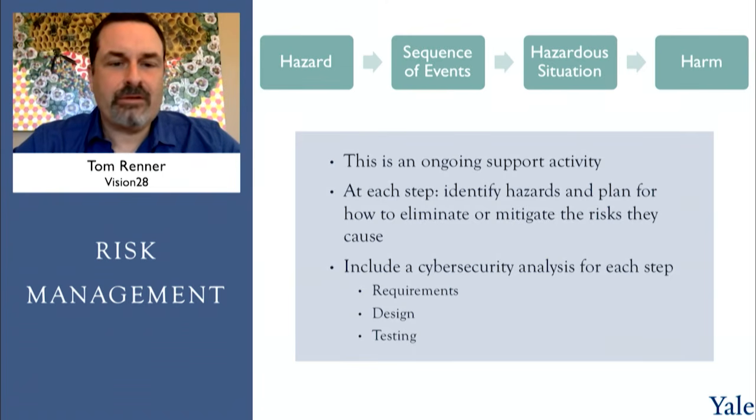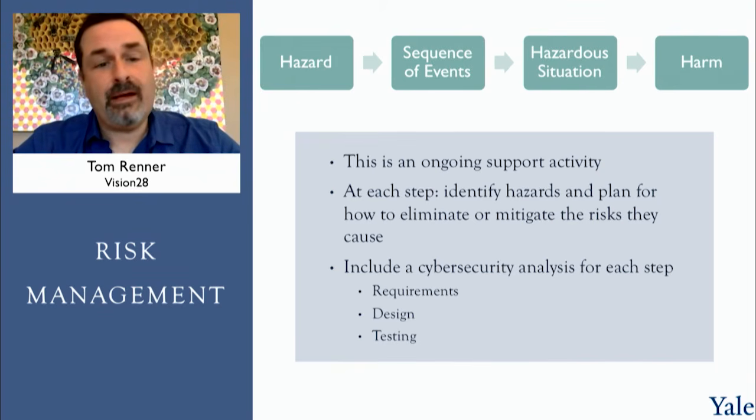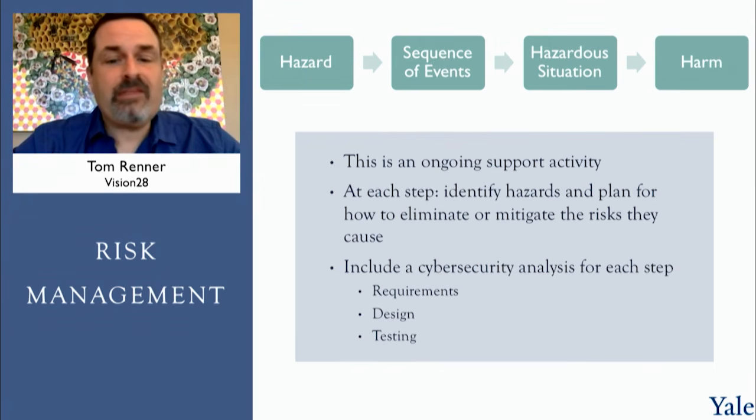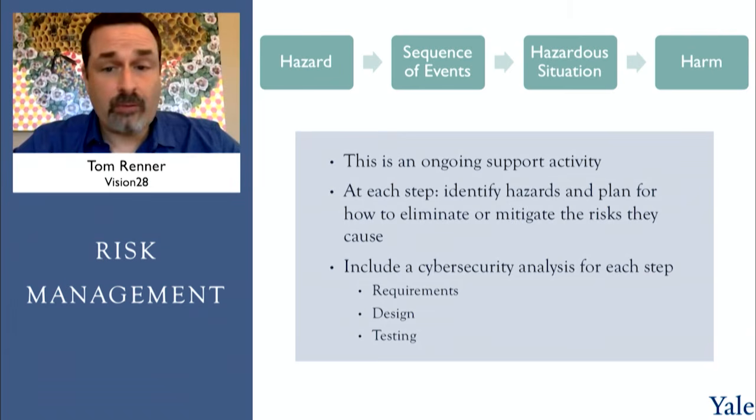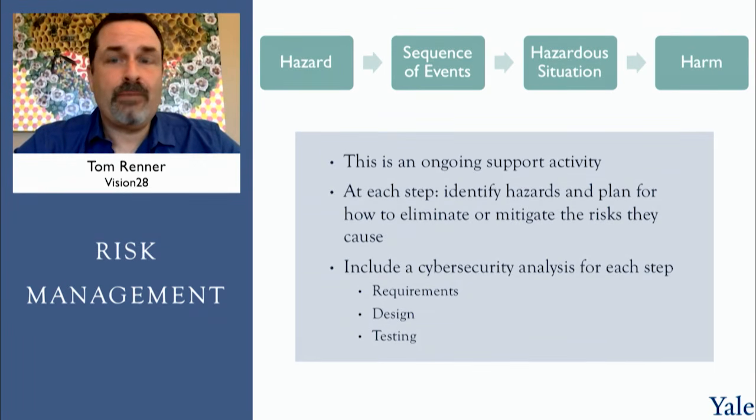Plan for cybersecurity when you're planning for your product, develop for cybersecurity as you're developing your product, and surveil, post-market surveillance for cybersecurity issues as your product's on the market. So that means having a plan so that you can get started early. As you're thinking about requirements and overall design, you should be thinking about cybersecurity.